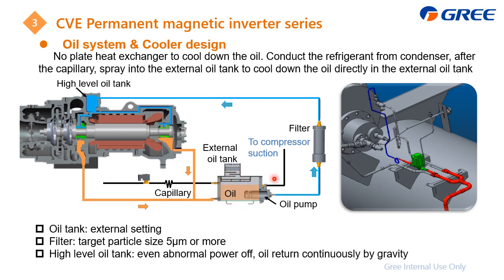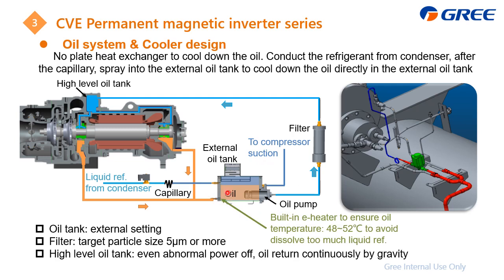And then we also use the refrigerant to cool it down. Instead of the plate heat exchanger, for this one we directly spray the refrigerant into the oil tank, controlled by a solenoid valve. This liquid is from the condenser, just after this capillary, and in the actual unit it will be located here. We spray this refrigerant into the oil tank to cool down the oil, and then the refrigerant becomes gas and flows to the compressor suction side. Besides, there is an e-heater located here to keep the oil temperature within this range, to avoid too much liquid refrigerant dissolving in the oil.